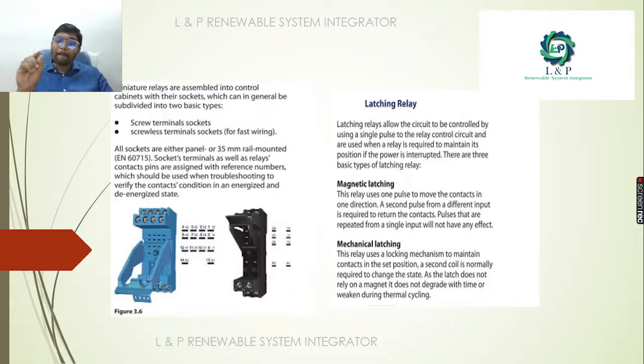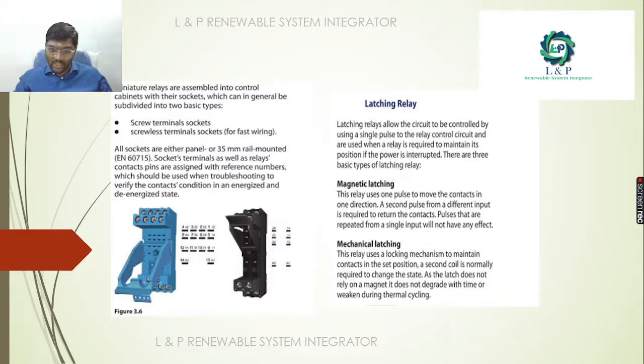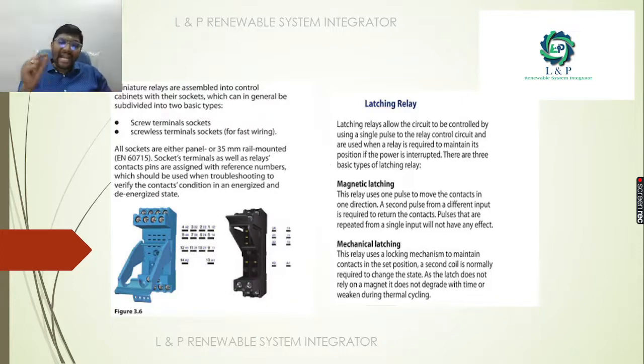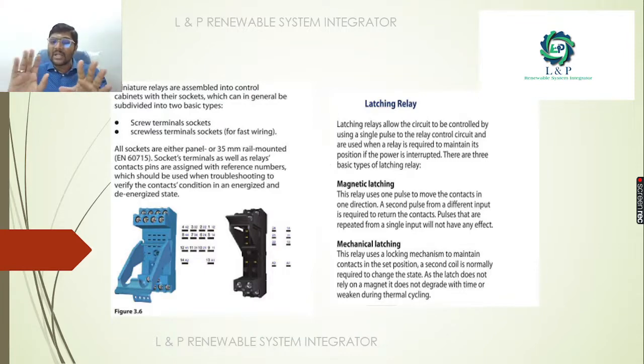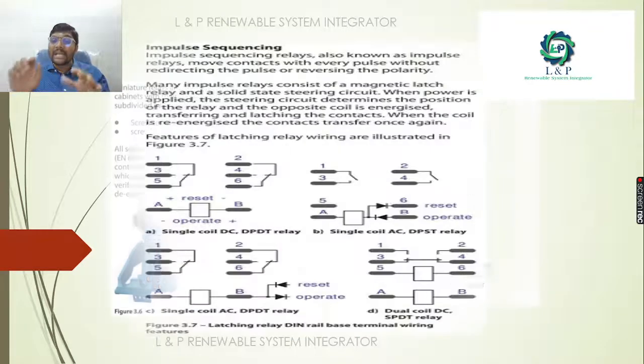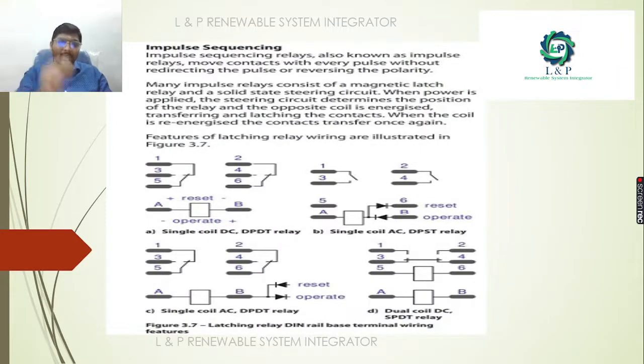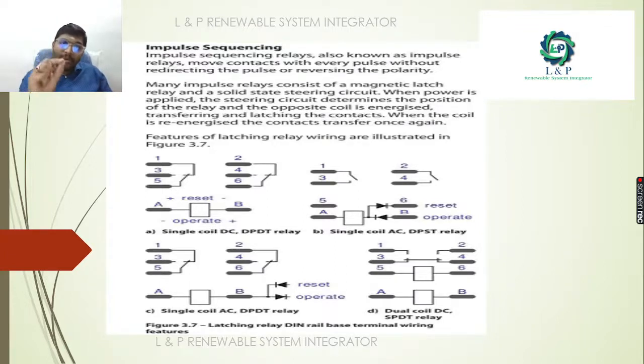In magnetic latching, the relay uses only one pulse to move the contact in one direction, and a second pulse from a different input is required to return the contact. In mechanical latching, the relay uses a locking mechanism to maintain the contact in the set position, and a second coil is normally required to change the contact. Since the latch does not rely on a magnet, it does not degrade with time or weaken during thermal cycling.